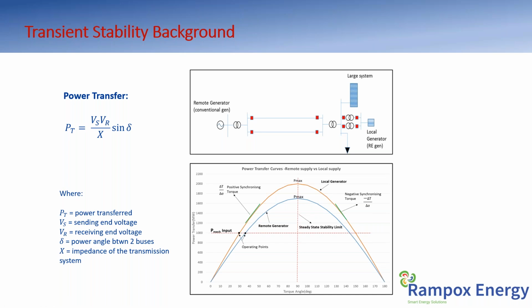That tells you that for stability purposes, you always want to keep your torque angles and rotor angles a bit lower. You don't want to open it up too much. The moment a generator operates at higher torque angles, it's a stability problem, exposing it to the risk that if something happens, it may run out of step. The rule of thumb is to be around 30 degrees or so.